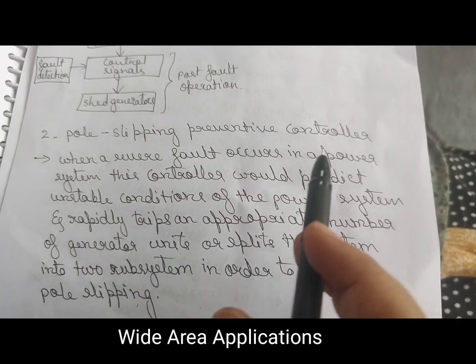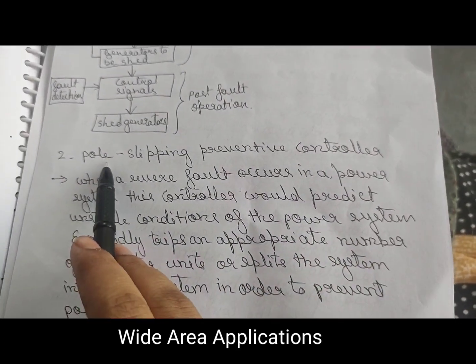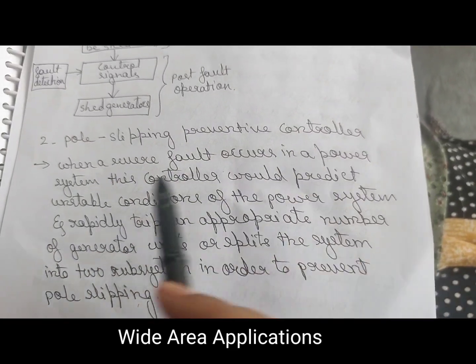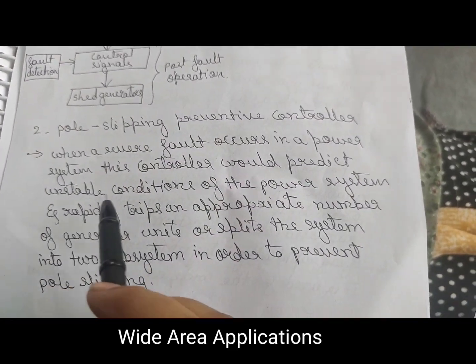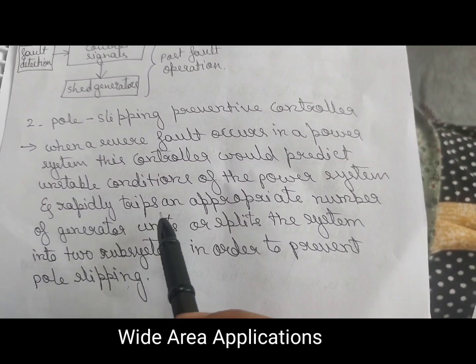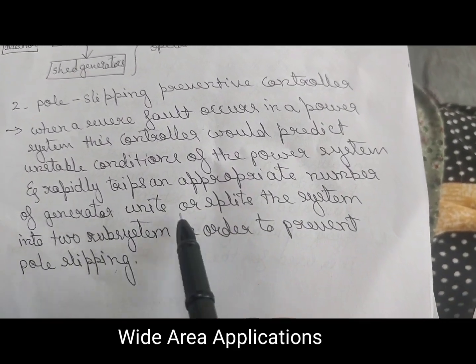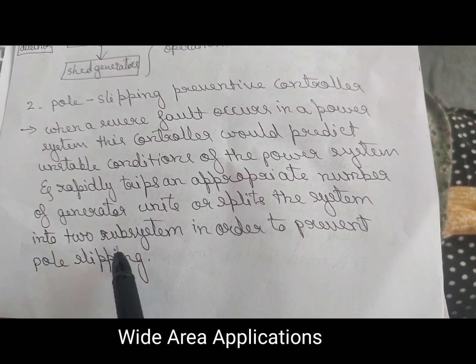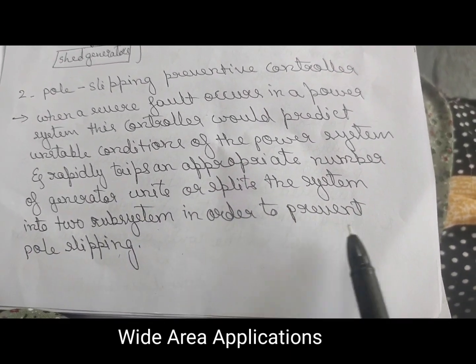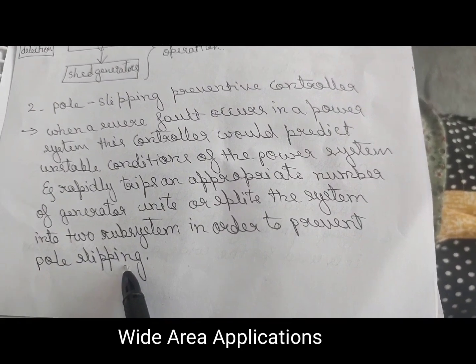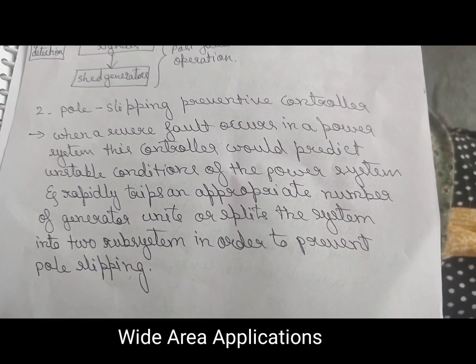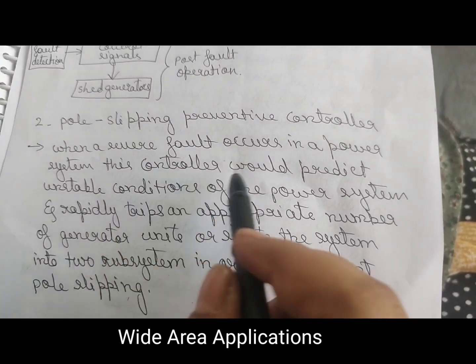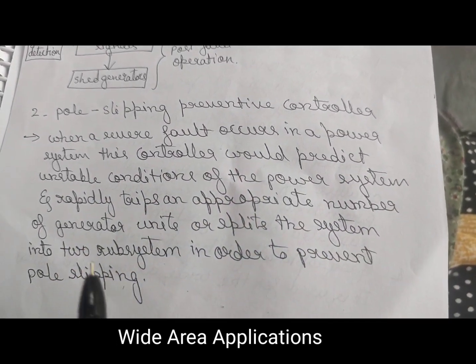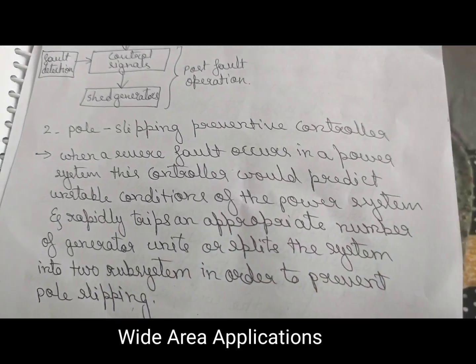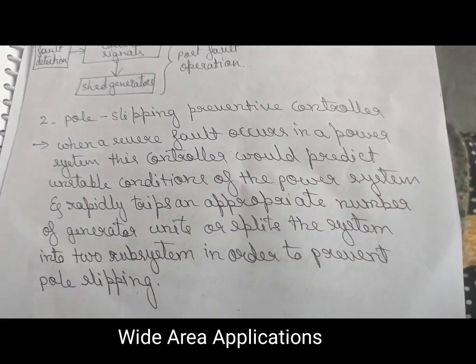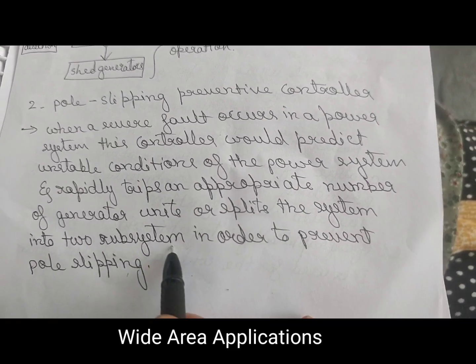Pole slipping preventive controller. When a severe fault occurs in a power system, this controller would predict an unstable condition of the power system and rapidly trip an appropriate number of generator units, or split the system into two subsystems, in order to prevent pole slipping.